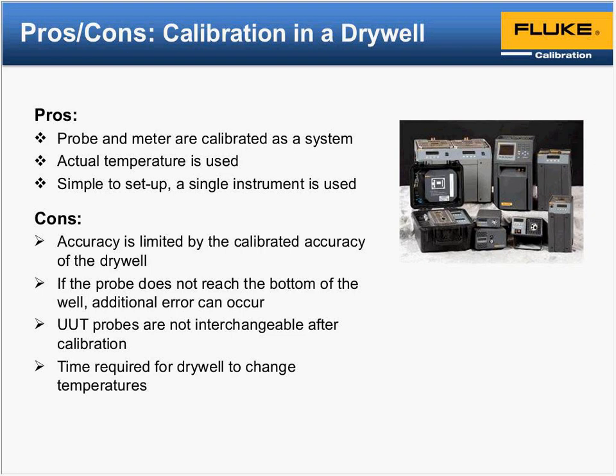Actually taking a very hard look at the probe's resistance versus temperature, and then the math. And with the readout piece, we're actually applying a known resistance or millivolt. So again, very straightforward there. In the certificates, you're going to see uncertainty provided for the probe, or in the case of the readout, what was applied, what was read, and the error, again very straightforward. And it allows you that versatility to have the flexibility. So if you have multiple probes on a single readout, it gives you some flexibility that way.